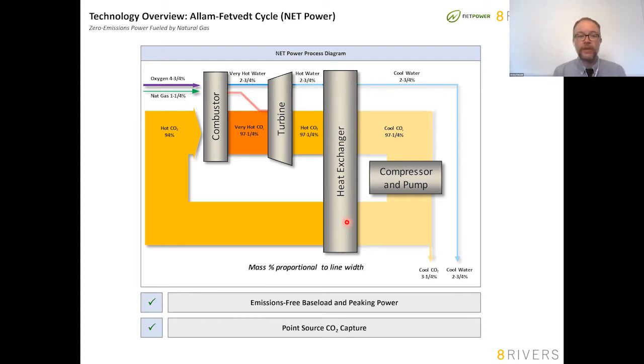We realized we can scavenge heat out of the air separation unit. The heat of compression from compressing the air to get it into the air separator is the correct amount and temperature we need in the power cycle to fix this imbalance in the heat exchangers. So what has historically been a negative parasitic load on the air separation unit, we turn into a positive, bringing it into the power cycle and ending up with a much more efficient power cycle.